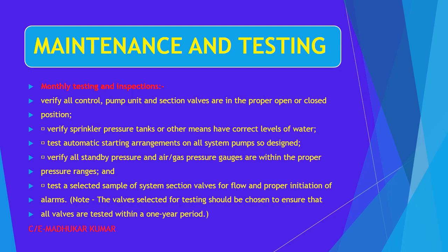That means the alarm testing: for each and every section we have a test valve, so we have to test it as per the matrix. Note that the valves selected for testing should be chosen to ensure that all valves are tested within a one year period. So we have a one year combined period, and in that all valves must be tested.